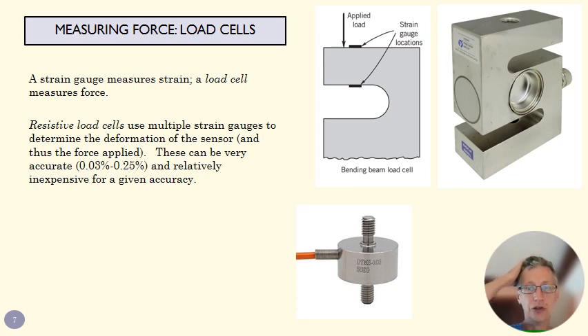We do that with a strain gauge. Think about a load cell that looks something like this. If I apply a force here, that's going to deform this metal. If I deform that metal and put some strain gauges in ideal locations, I'll be able to figure out how much strain there is. That allows me to do some analysis and figure out how much force there is. A load cell is essentially just a tool that uses strain gauges to figure out what forces are.